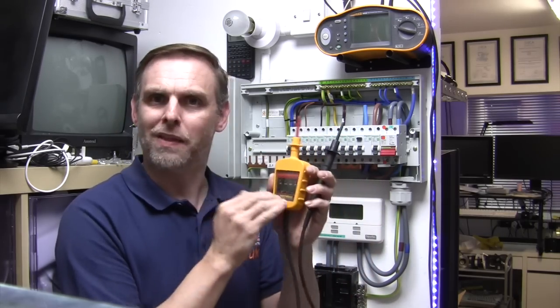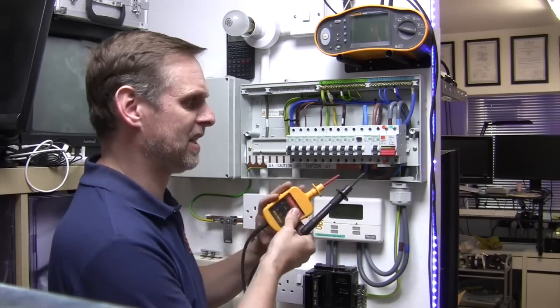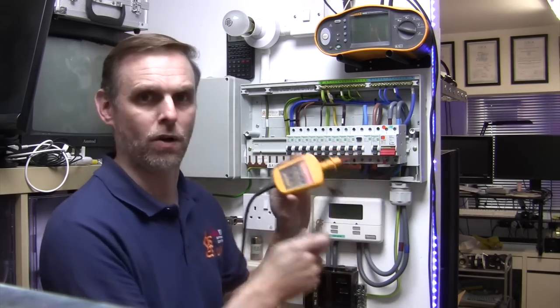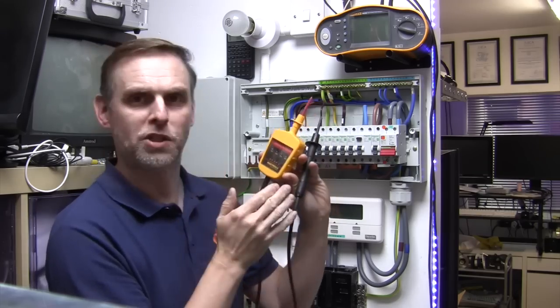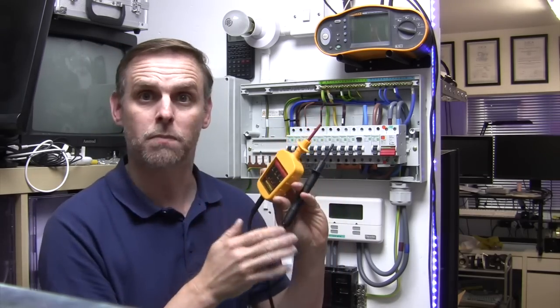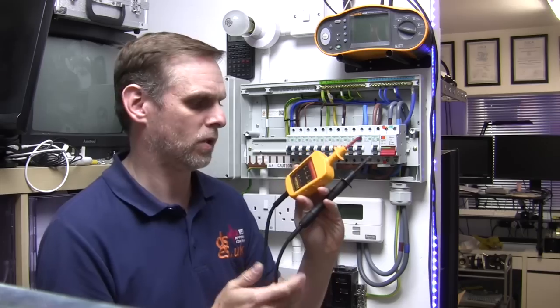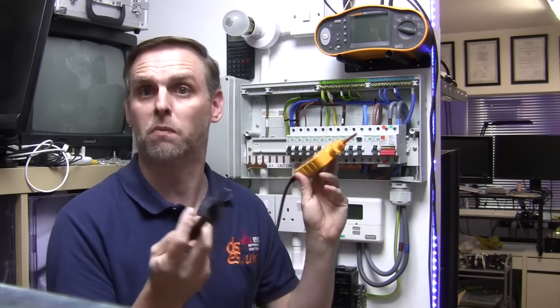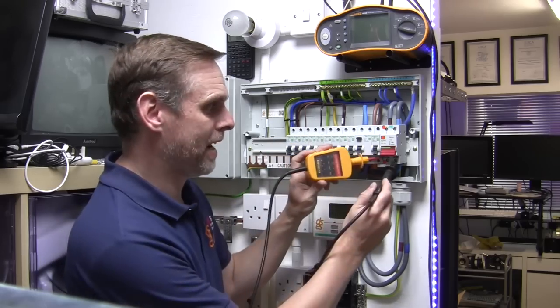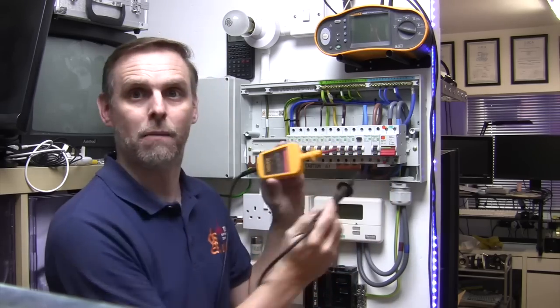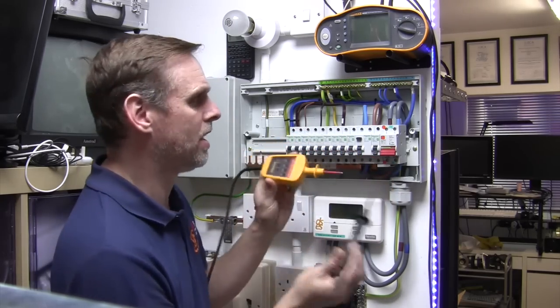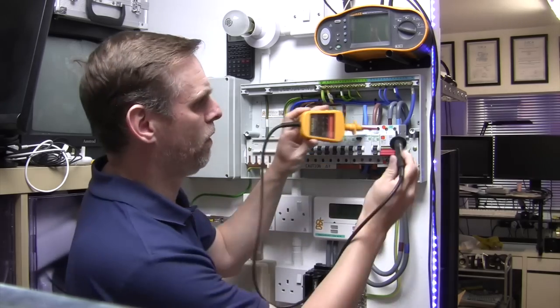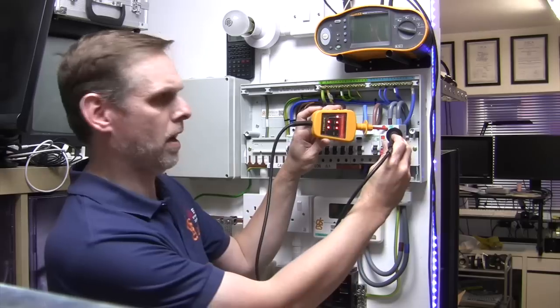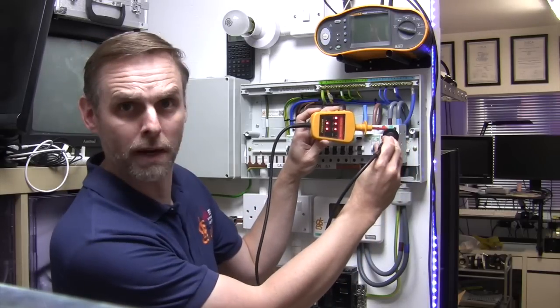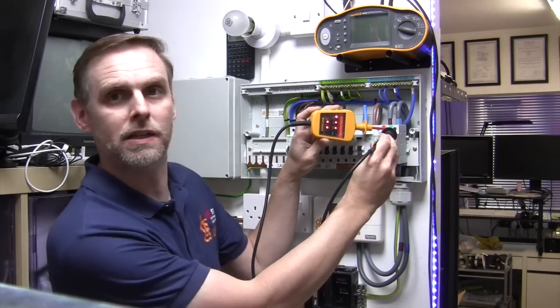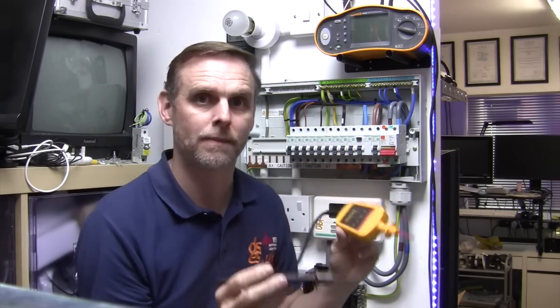But how do I know that this thing is still working and that it truly is giving me an actual dead result and it's not a failure of the voltage indicator? Obviously we have just proven it, but maybe using it on the proving unit has caused a problem. Maybe it's blown a fuse within here or something like that. So once I've got my dead reading, I need to re-verify that my voltage indicator is actually still good. And we can do that by putting it back on the proving unit or onto a known good source of supply, such as in this case the input to my main switch, and we can see there that yes indeed my voltage indicator is still working.